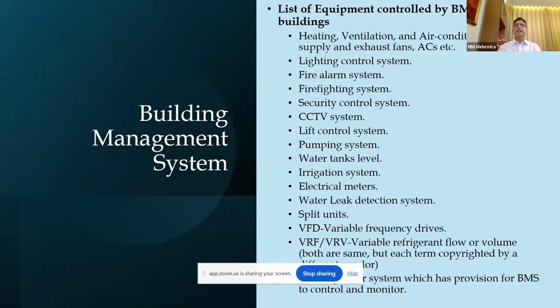Now, these are the items which are covered by that BMS: heating, ventilation, air conditioning, lighting control, fire alarm, firefighting, security, CCTV, lift, pumping, water tanks level, irrigation system, electric meters, water leak detection system, split units. Then there are variable frequency drive. Variable frequency drive is basically part of your air conditioning system. So things like that.